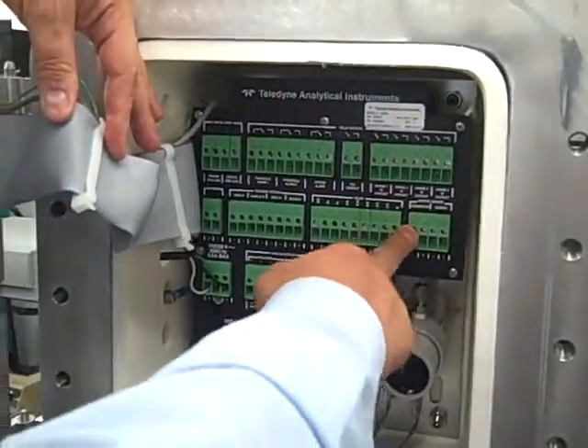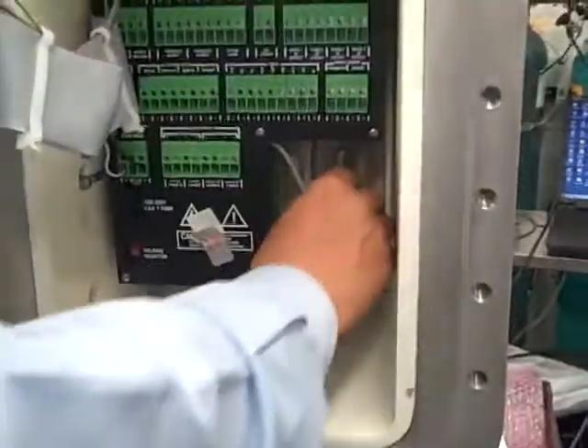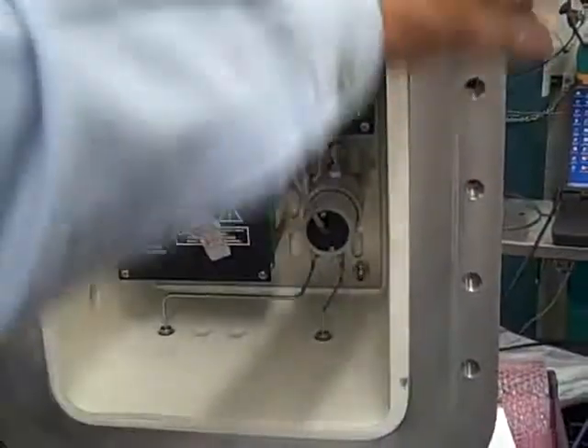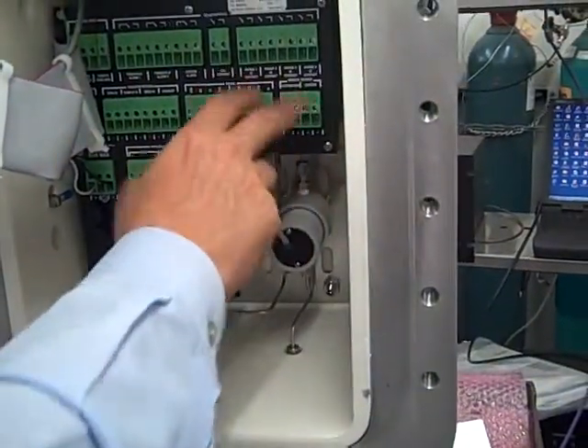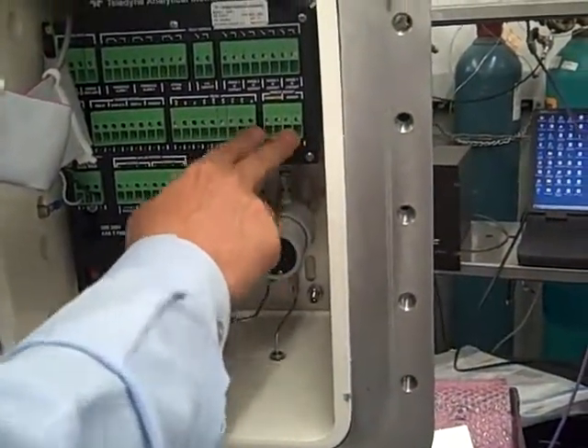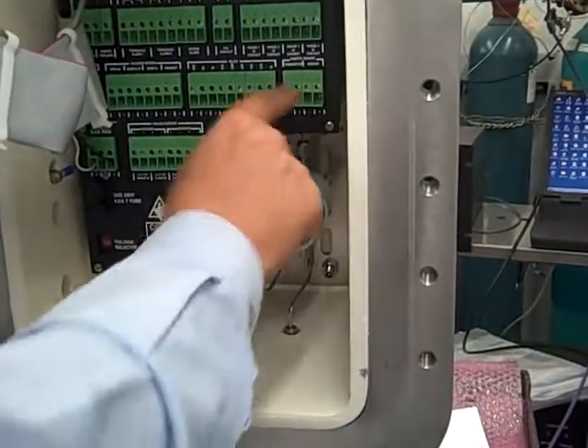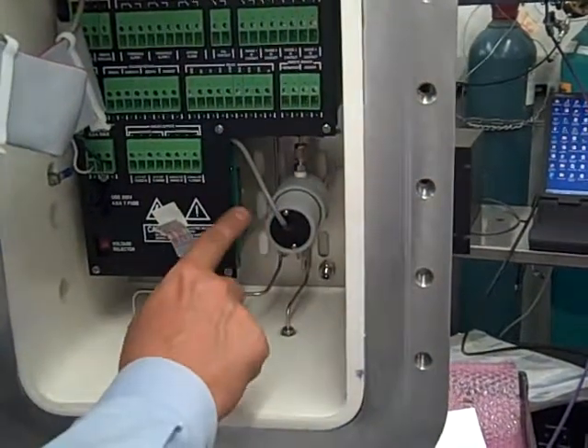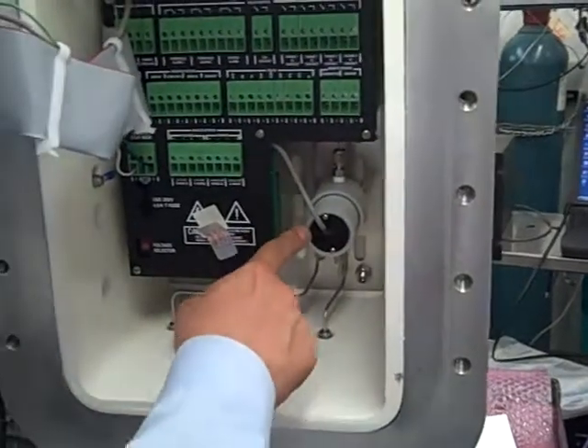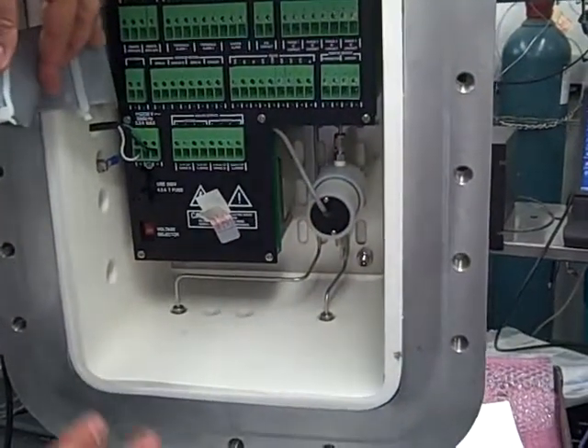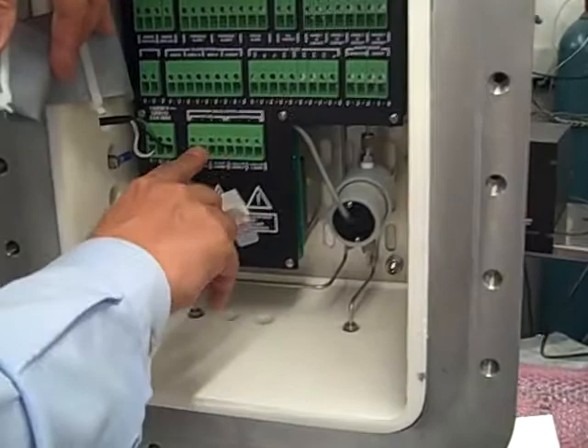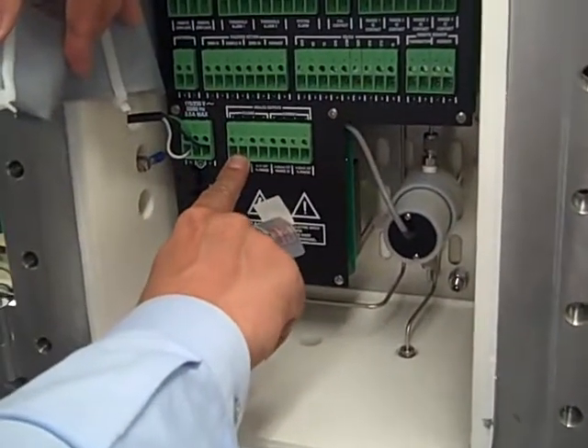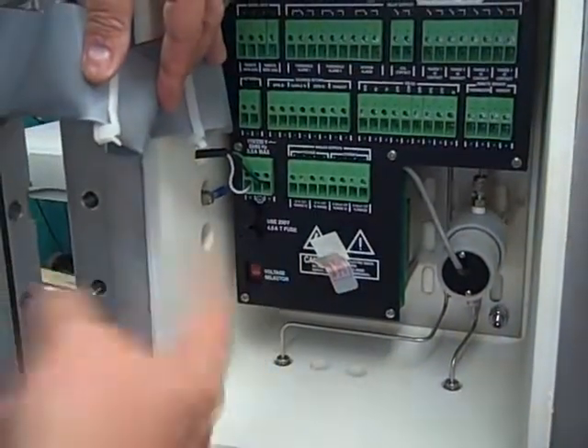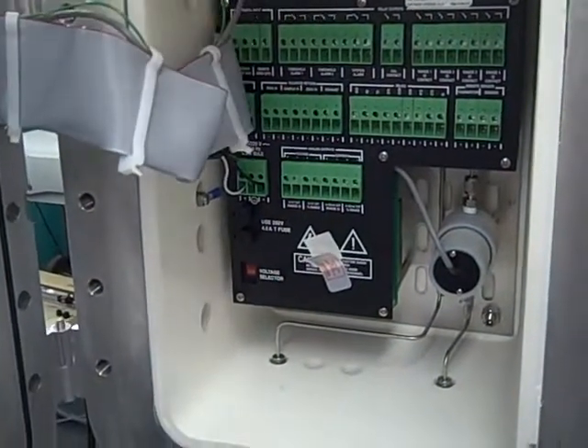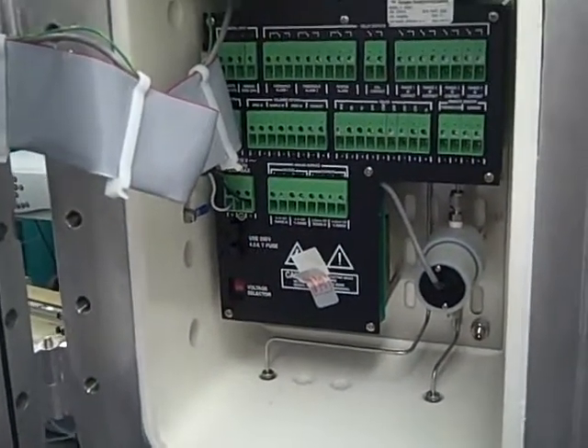If you want to connect a sensor remotely, in some of our units, the sensor, instead of being inside the explosion-proof housing, is mounted remotely, and there are 4 wires that come from that type of setup, 2 of which are for the sensor, the other for the temperature compensating thermistor inside of the sensor block. Also, most importantly, we have two analog outputs in voltage, 0 to 1 volt, two 0 to 1 volt signals, one of which tells you the percent of range.